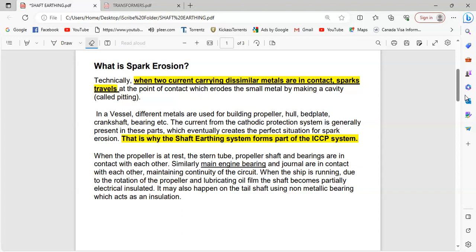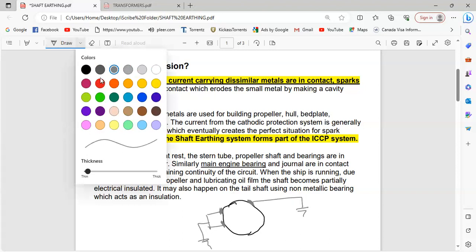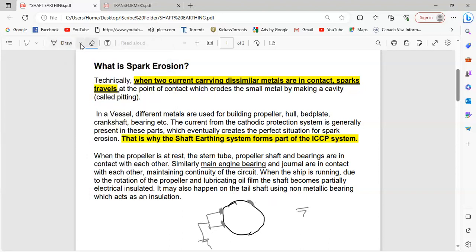But here, it's hard enough that it doesn't wear down easily. These brushes have to be making proper contact — suppose this is the shaft, it's not a perfect circle, so the brushes have to maintain contact. There is generally a third one also. Two of these are taken and given directly to drain out the charge, and this one is taken as the earth for your meter.